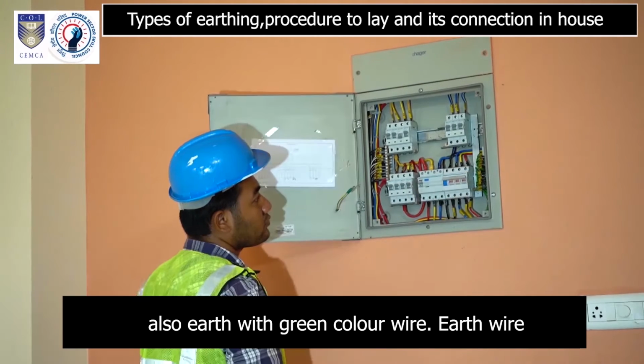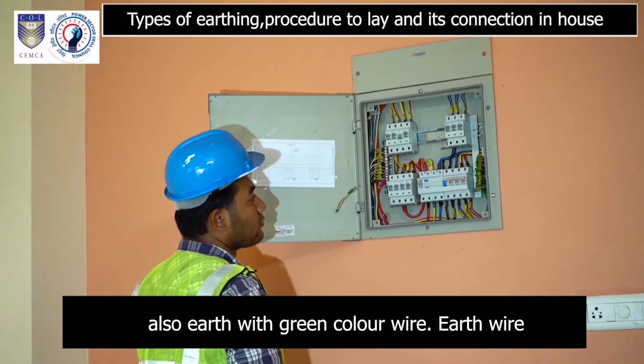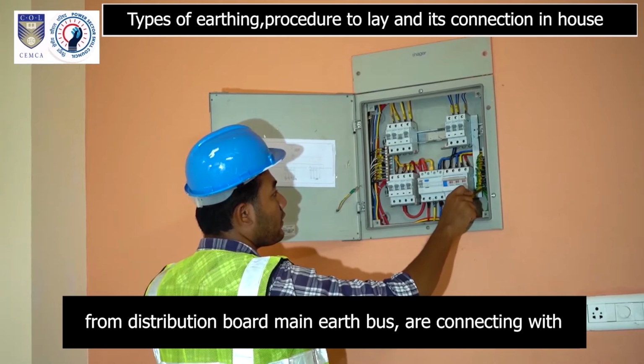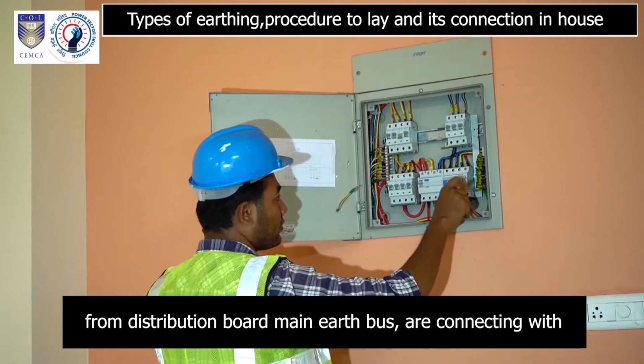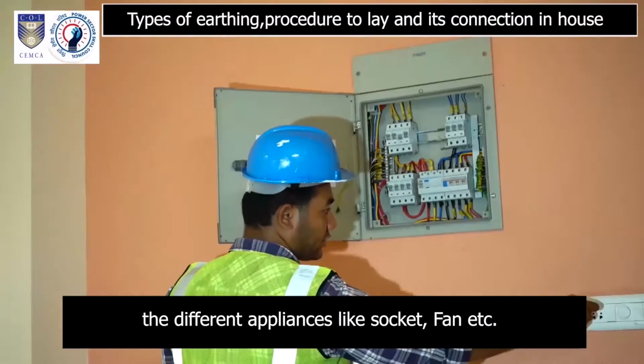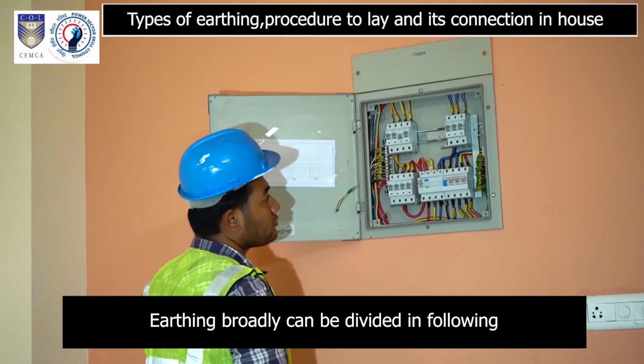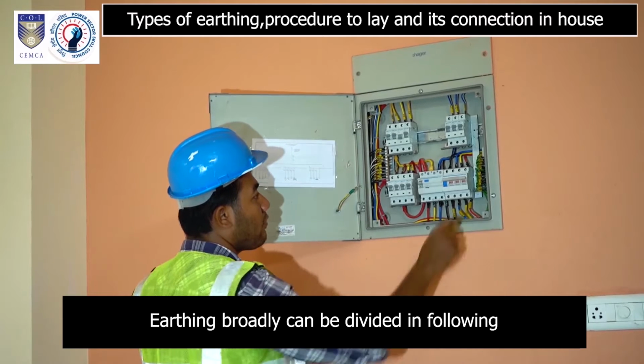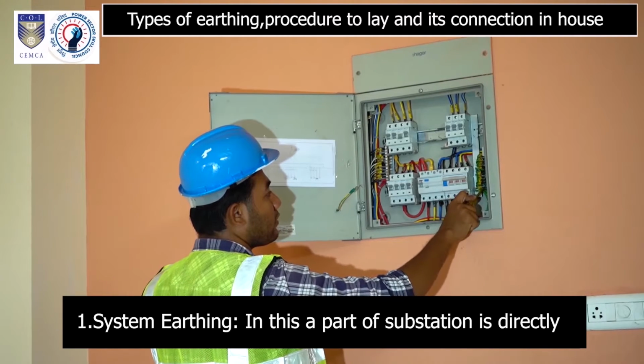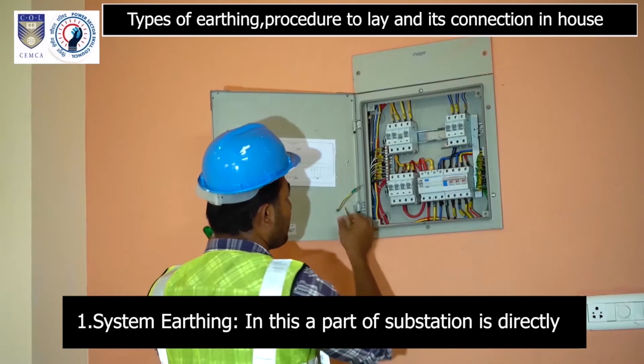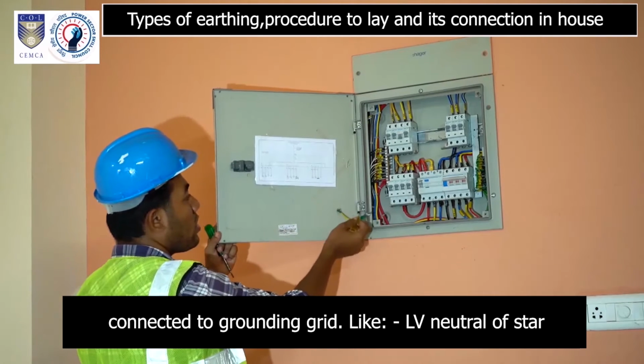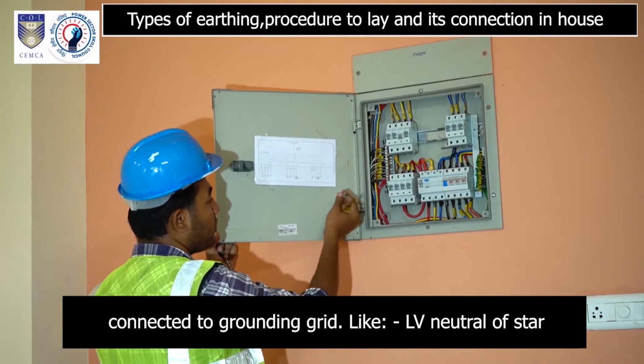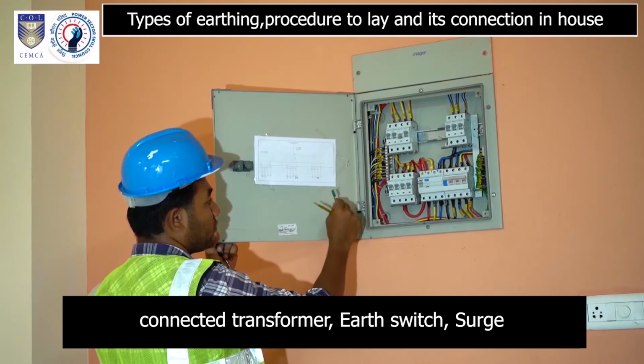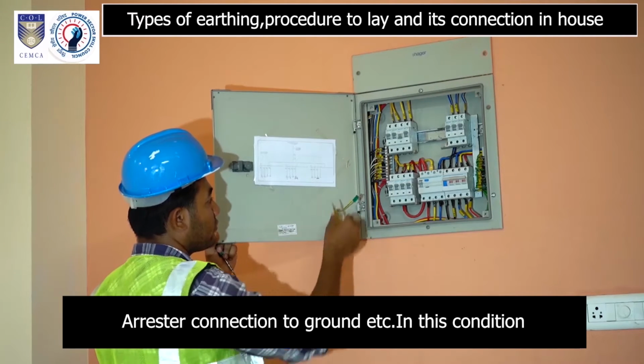The distribution board main door is also earthed with a green color wire. Earth wires from the distribution board main earth bus are connected to the different appliances like socket, fan, etc. Classification of earthing. Earthing can broadly be divided as follows. 1. System earthing. In this, a part of the substation is directly connected to the grounding grid, like the LV neutral of a star connected transformer, earth switch, surge arrestor connection to ground, etc.